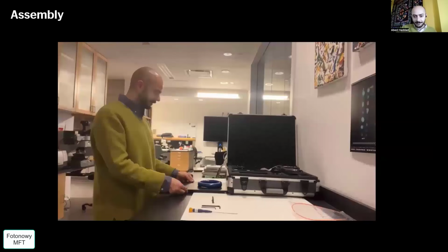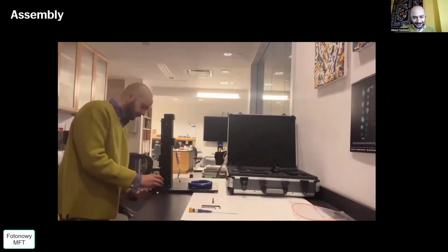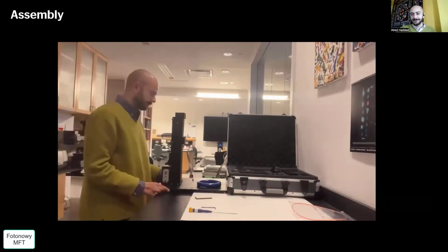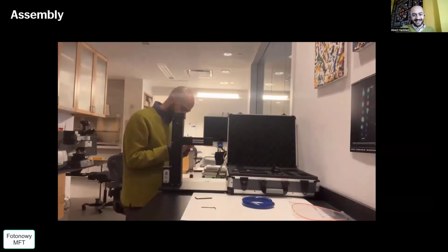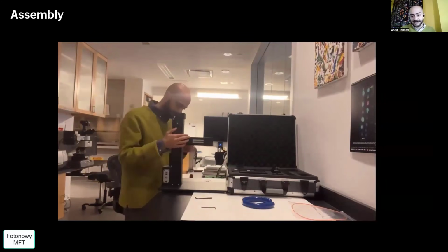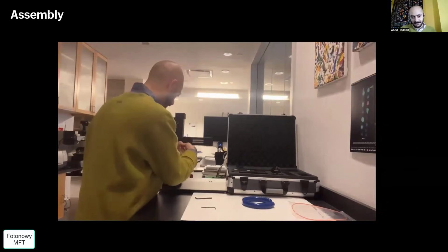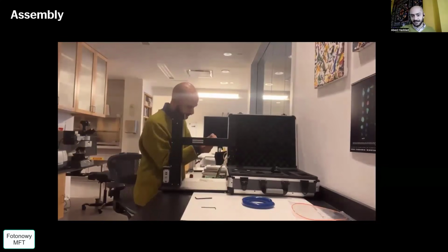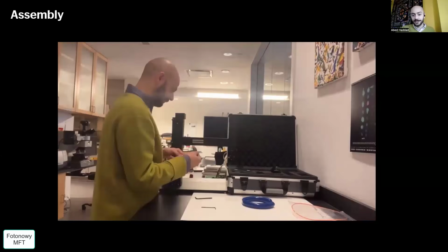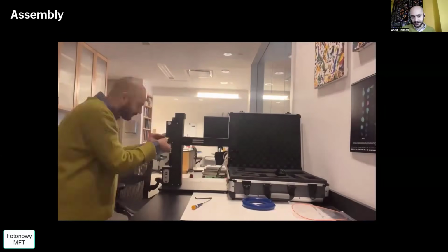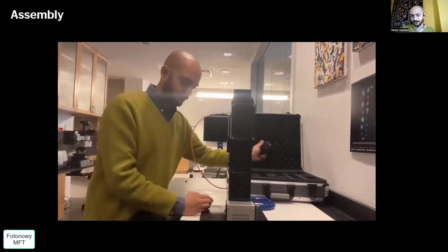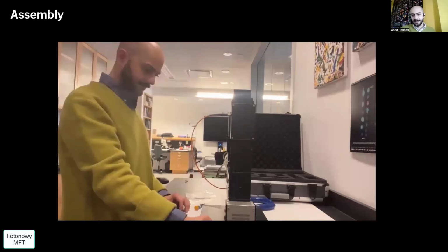So I made a little stop motion animation, I guess, so a little video. You can see me putting together the MFT. I didn't realize I'm wearing the same sweater that I'm wearing right now. But as you can see, it's quite simple to put together. It takes about 5 minutes to dismantle and about 5 minutes to put together. And so I find it to be a really attractive feature of this particular instrument because it allows us to take it to different places and use it on site, be it at storage or sometimes in the galleries.